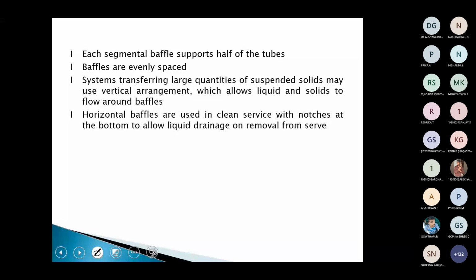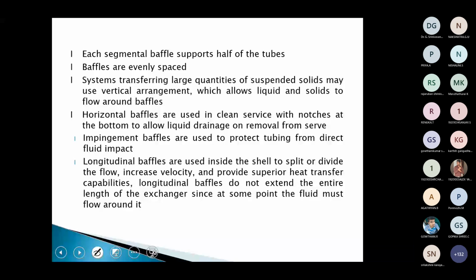So horizontal baffles are used in clean service. That is why we are going for horizontal baffles. Sometimes we use impingement baffles. They are used to protect the tubes from direct fluid impact. When the fluid enters at a high pressure, if it hits the tubes, the tubes may be exposed to high pressure. It may lead to breakage. So in order to prevent this, the impingement baffles are provided at the inlet end of the heat exchangers.